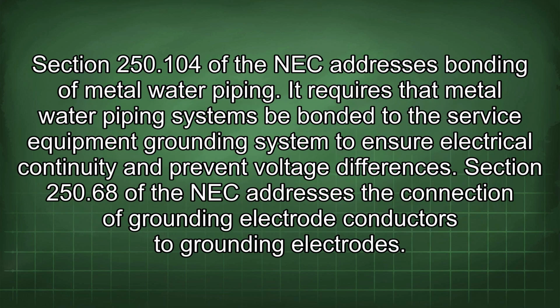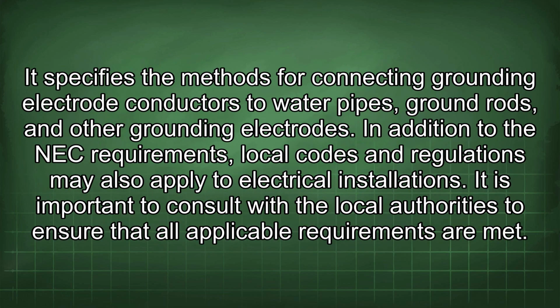Section 250.104 of the NEC addresses bonding of metal water piping. It requires that metal water piping systems be bonded to the service equipment grounding system to ensure electrical continuity and prevent voltage differences. Section 250.68 of the NEC addresses the connection of grounding electrode conductors to grounding electrodes. It specifies the methods for connecting grounding electrode conductors to water pipes, ground rods, and other grounding electrodes.